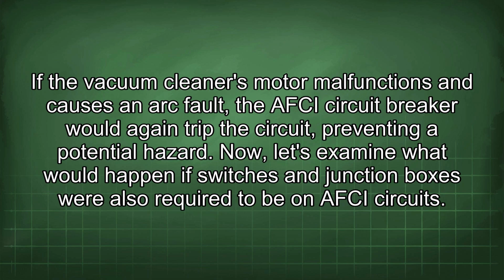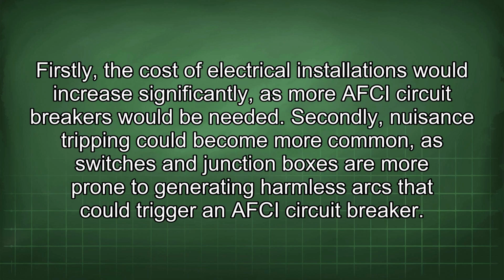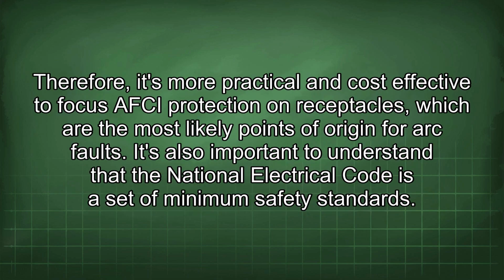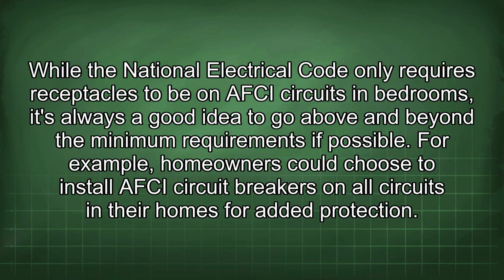Now, let's examine what would happen if switches and junction boxes were also required to be on AFCI circuits. Firstly, the cost of electrical installations would increase significantly, as more AFCI circuit breakers would be needed. Secondly, nuisance tripping could become more common, as switches and junction boxes are more prone to generating harmless arcs that could trigger an AFCI circuit breaker. Therefore, it's more practical and cost-effective to focus AFCI protection on receptacles, which are the most likely points of origin for arc faults. It's also important to understand that the National Electrical Code is a set of minimum safety standards. While the National Electrical Code only requires receptacles to be on AFCI circuits in bedrooms, it's always a good idea to go above and beyond the minimum requirements if possible.